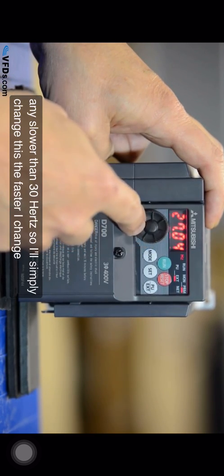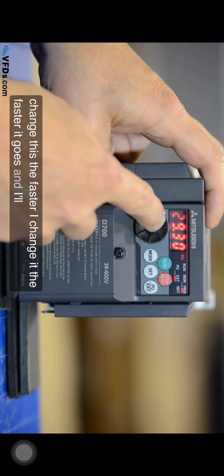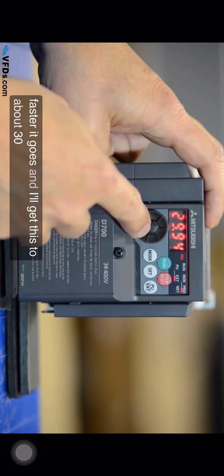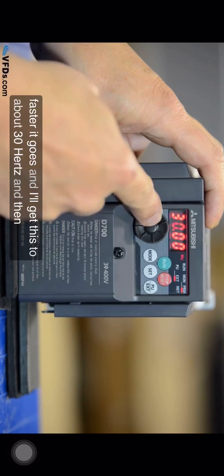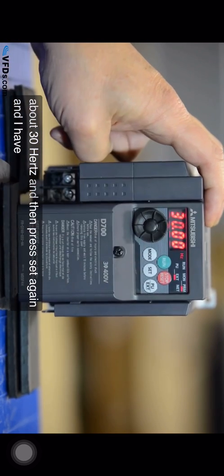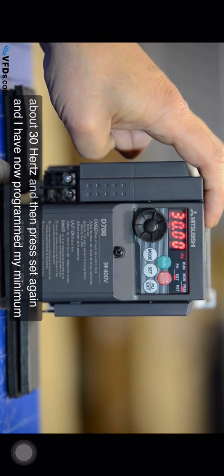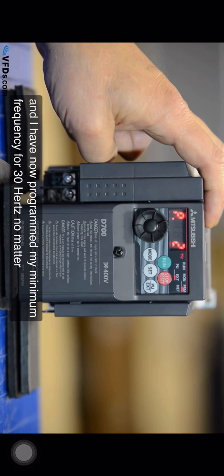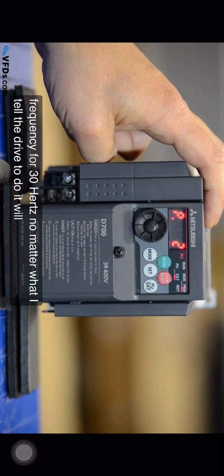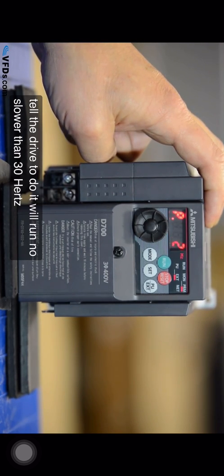The faster I change it the faster it goes and I'll get this to about 30 hertz and then press set again and I have now programmed my minimum frequency for 30 hertz. No matter what I tell the drive to do it will run no slower than 30 hertz.